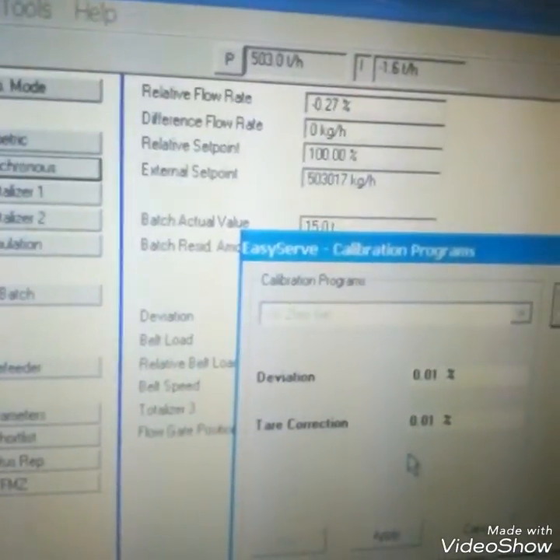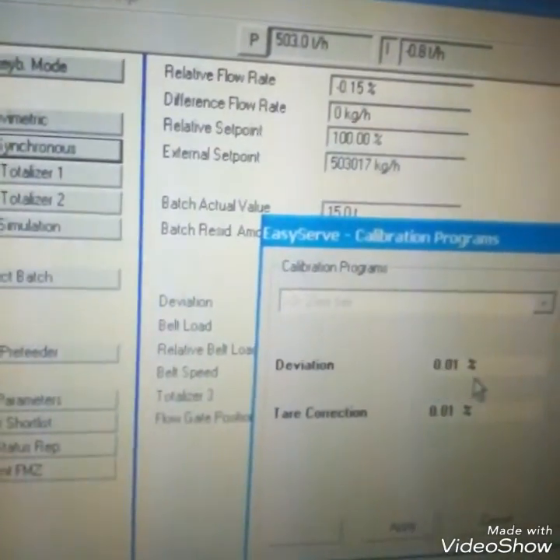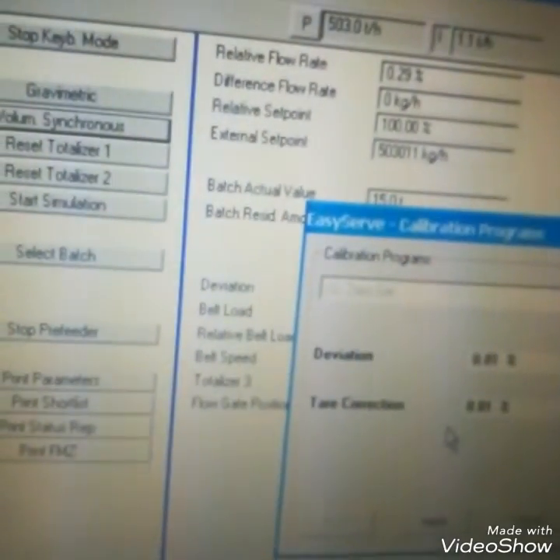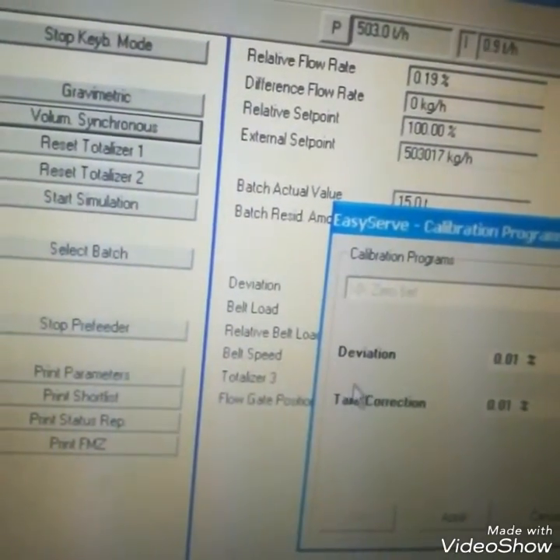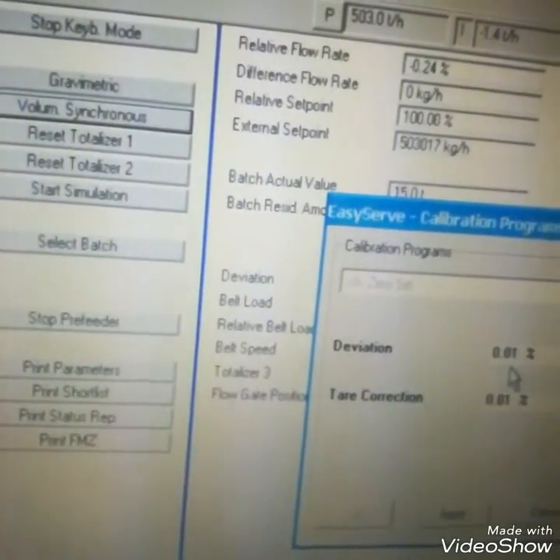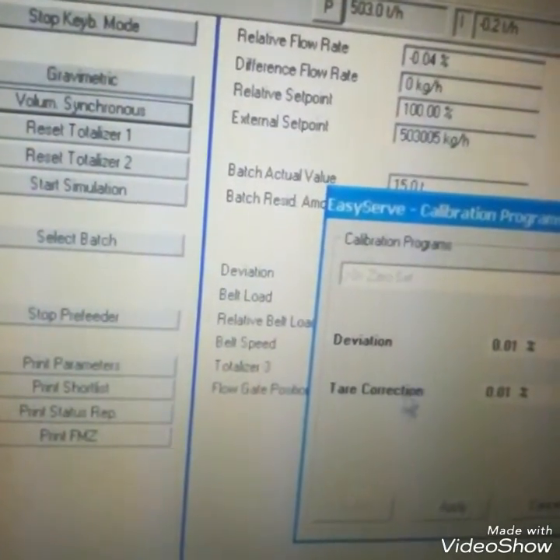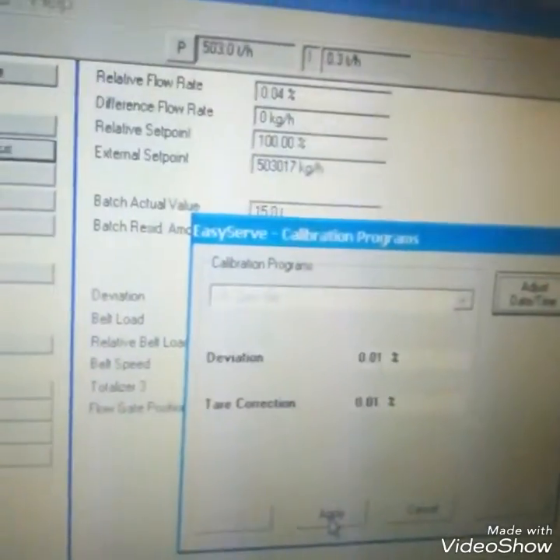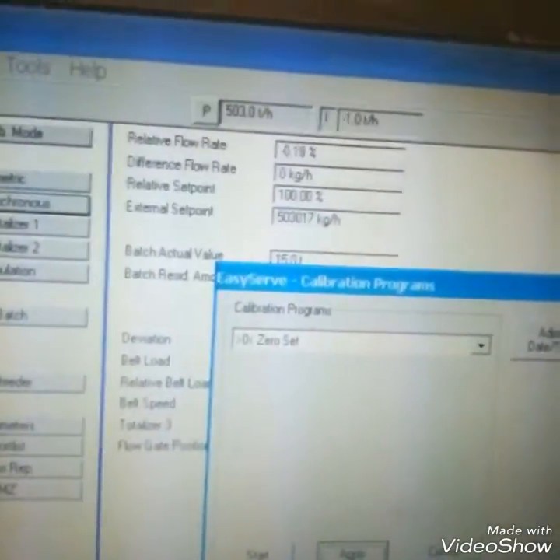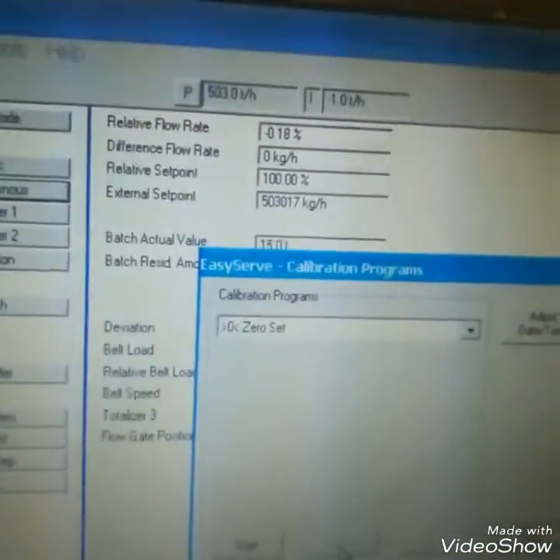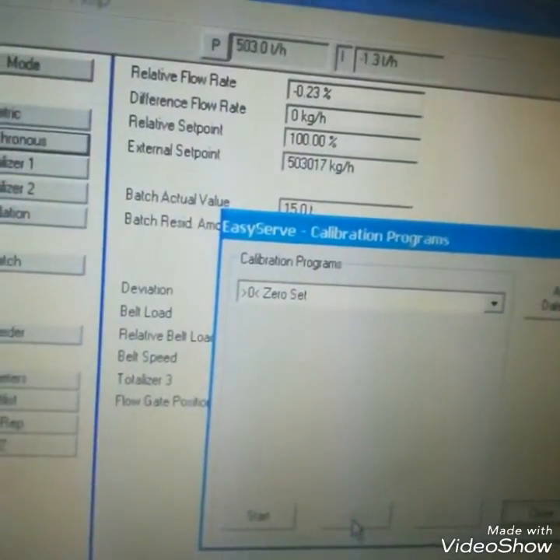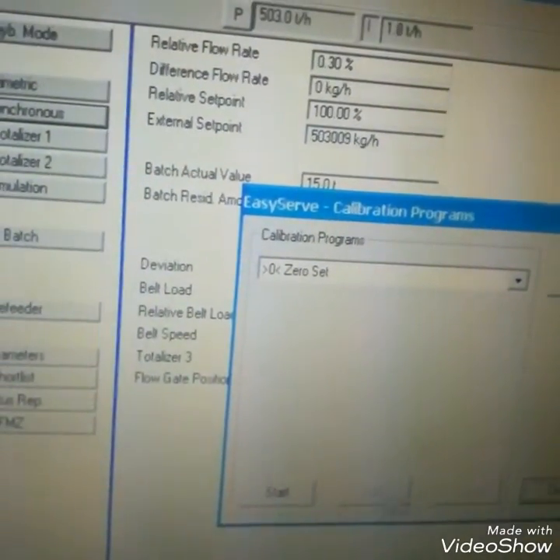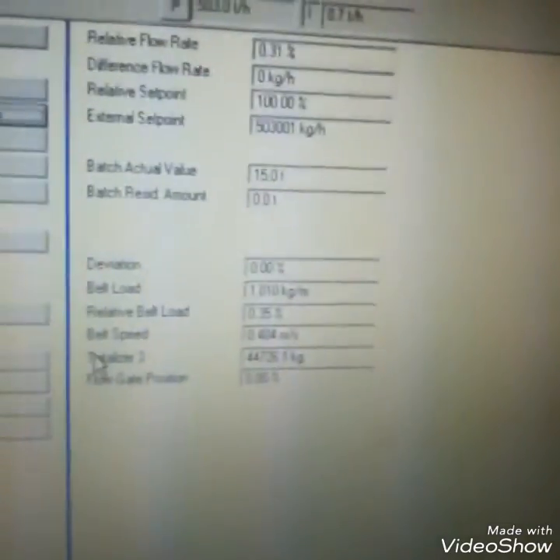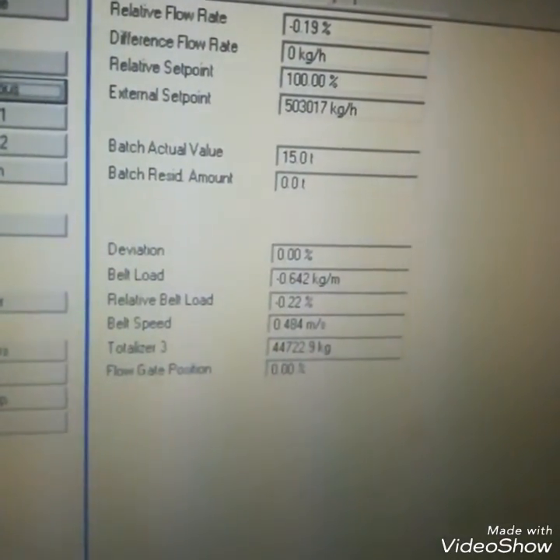How to zero calibrate belt weigh feeder with Schenck EasyServe software. You can see the deviation, that is how much deviation was there, and the tare correction, how much tare was corrected. If I apply it, then it will take the new calibration value and it will be zero calibrated.